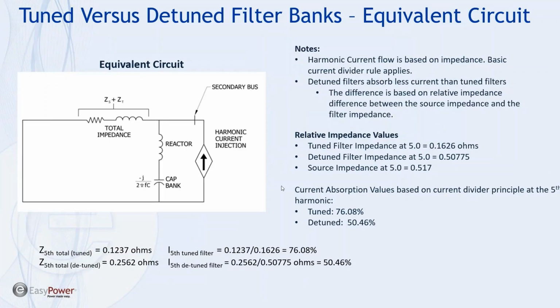So the notion that a detuned filter does not take in harmonic currents is just totally wrong. It's based upon the ratio of impedances. If you think about the impedance of the source, this can impact how much current flows into this filter branch here. A higher source impedance here means more current flows into your filter. Whether it's tuned or detuned, it means more current will flow into your filter. And this is something to always consider.